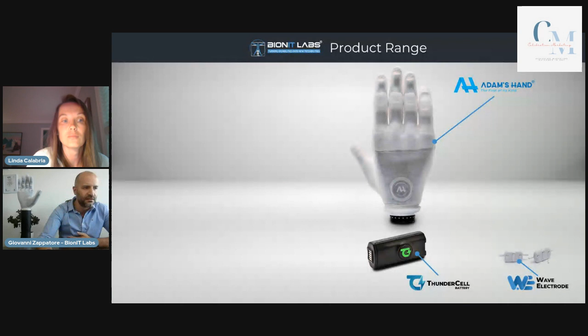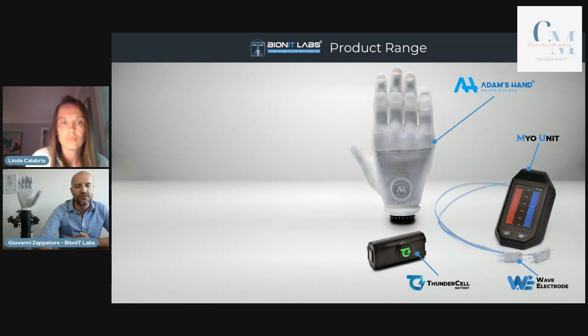Okay. So as I was telling you, the product range, ThunderCell battery is an external battery. Wave electrodes are standard analog electrodes, but thinner. So just 8 millimeters versus the standard of 1 centimeter. The Myo unit is a unit that you can use to test the patient Myo signals. The demo unit is the tower you see here to check the device functioning, to test it, and so on.